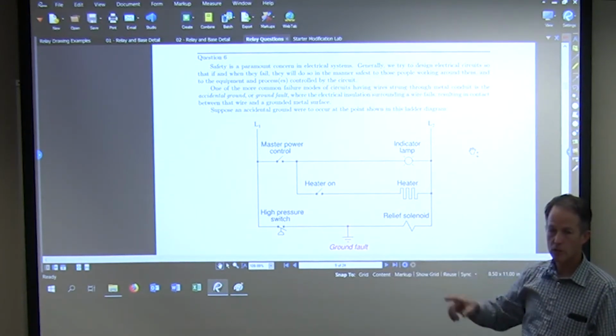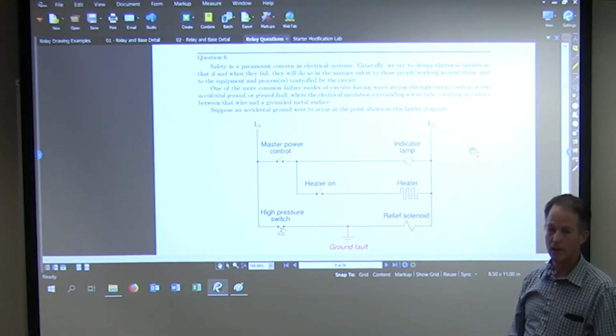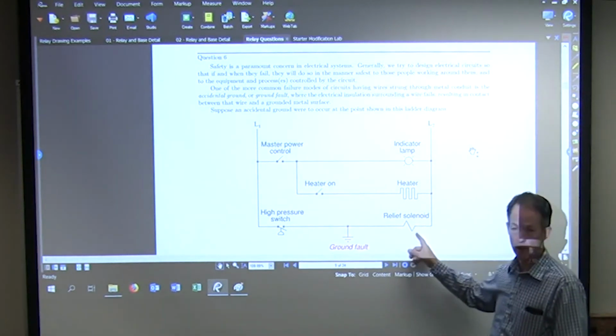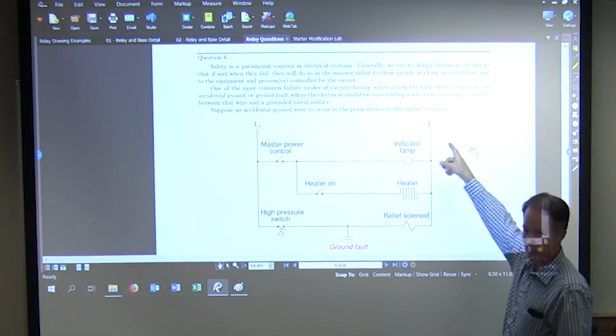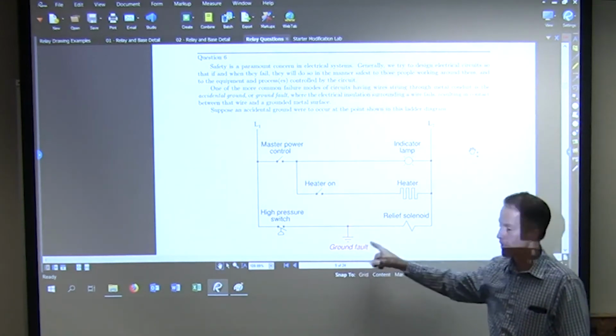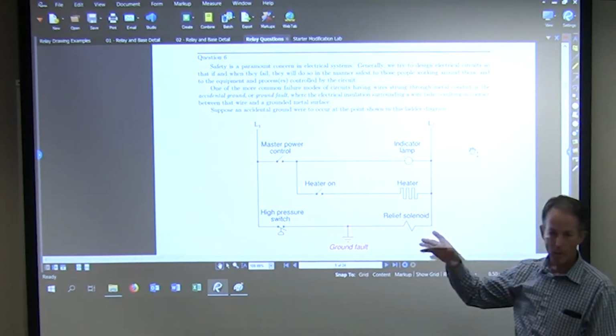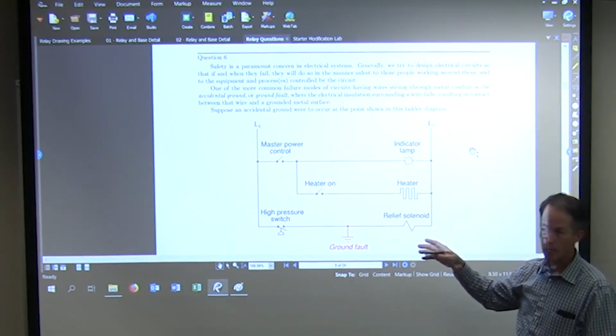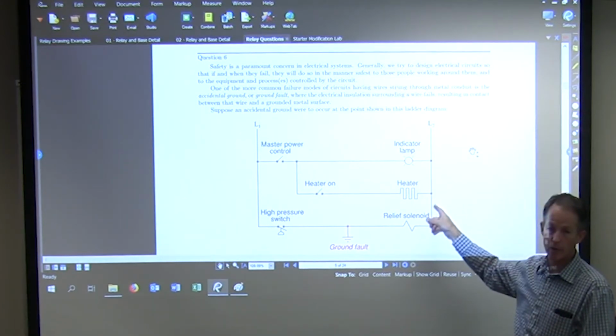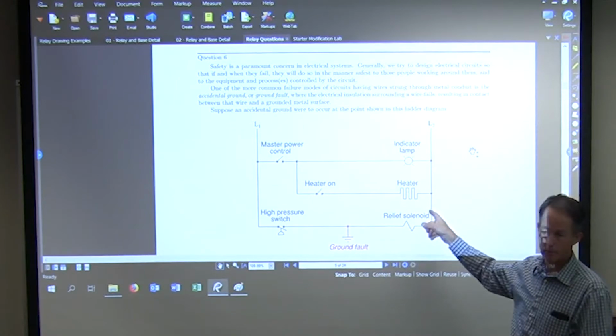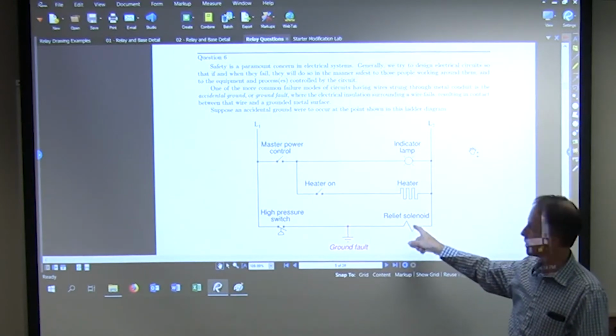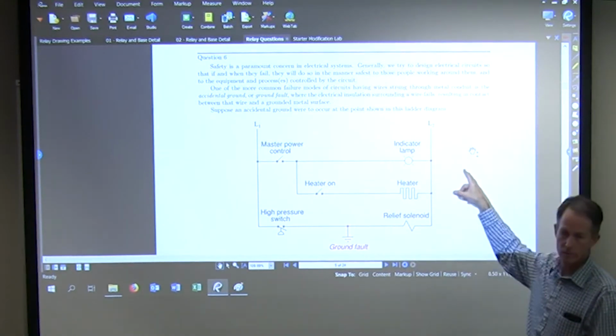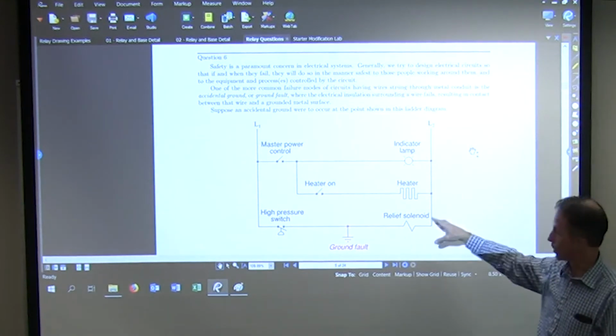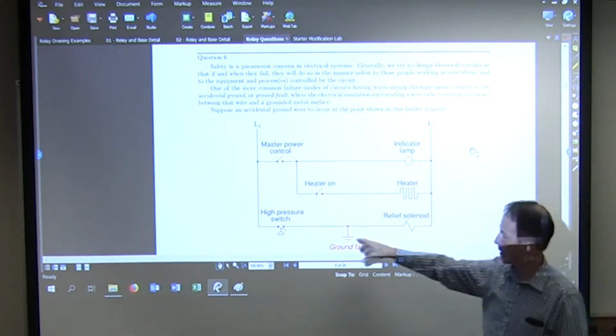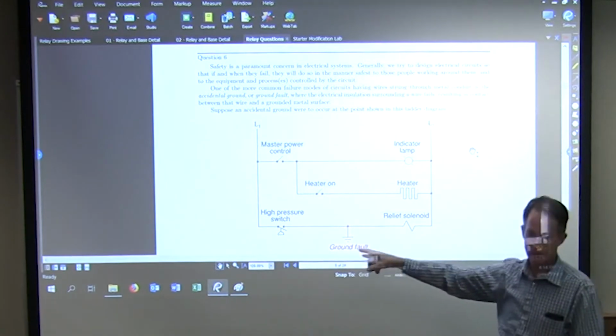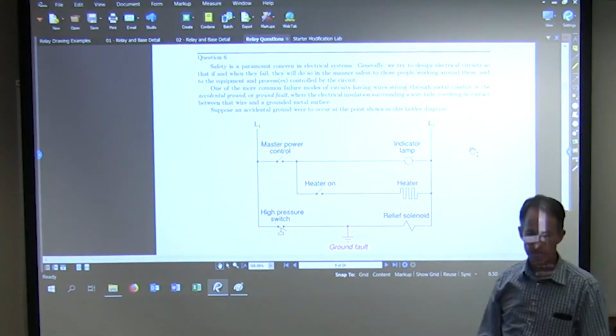Actually, you run like it's a 110 solenoid. Yeah. So if this is a 240 solenoid, I've got 120 volts flowing there. This is going to chatter and warm up, but it's not going to trip the circuit because it won't pull enough current, right? Because of the resistance, this is built for 240 volts. Okay. Will it work right? Okay. What happens if my pressure switch makes? Then you're going to go, right? Just like the other. Okay.